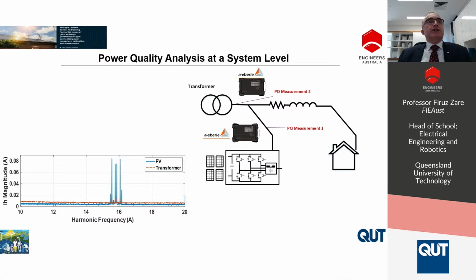This is a very interesting test result that we did in a network. This is a solar farm connected to one residential area. If you look at the blue line, you see that the harmonics coming from the solar inverter do not pass through the transformer to the grid. They circulate in the residential area, and that's the main reason that in residential areas we have lots of capacitive filtering in home appliances and different filters and equipment. Capacitor means low impedance at high frequency, which can create some immunity issues.